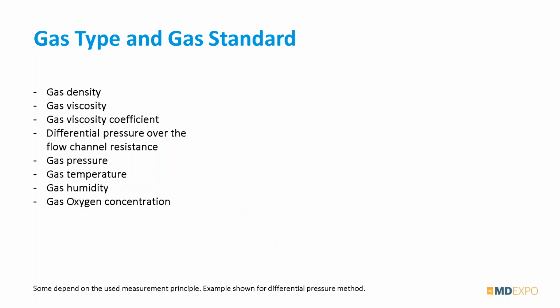Very important. All right, let's talk a little bit more about gas characteristics. We have things like the gas density, viscosity, and the viscosity coefficient. Those are pretty much dependent upon what gas you're measuring, right? And that is something you might have to actually enter into your analyzer. You can say, I'm measuring air, I'm measuring oxygen, I'm measuring a mix of the two, okay? We'll talk in a minute about some analyzers can tell you what the mix is. Then we have the condition, again, of the gases. For example, we have the differential pressure over a flow channel resistance. Some analyzers use a small resistance in the flow to create a difference in pressure so that they can convert that to a flow measurement.